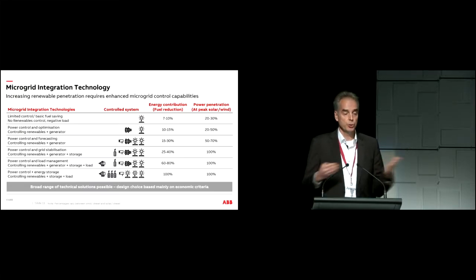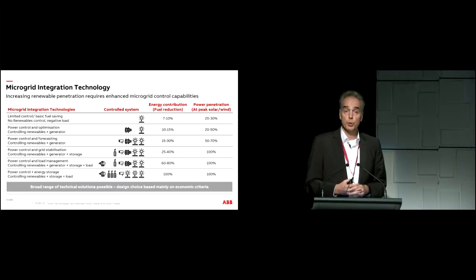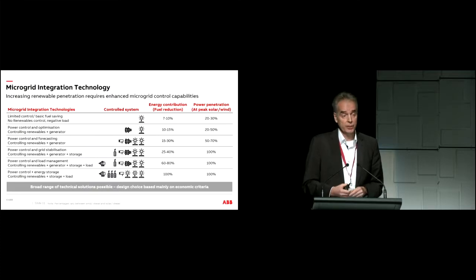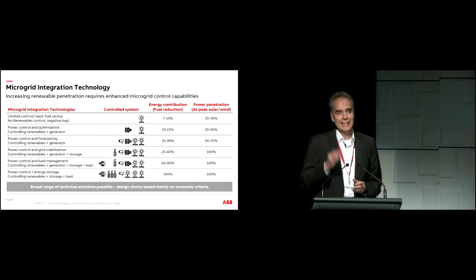First of all, there are 2 terms being used. The first we call energy contribution, which reflects the fuel reduction we can achieve. And the other term is power penetration, which is the instantaneous output of the wind or solar against the load. The peak power penetration will always be higher than energy, because that determines how much integration and stabilizing we have to introduce.